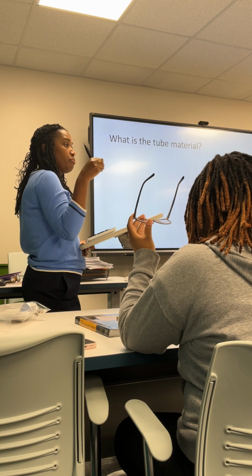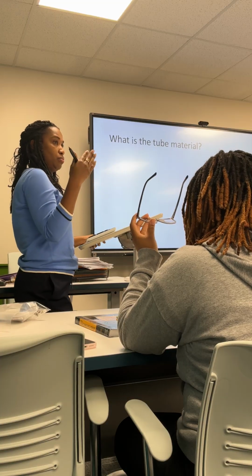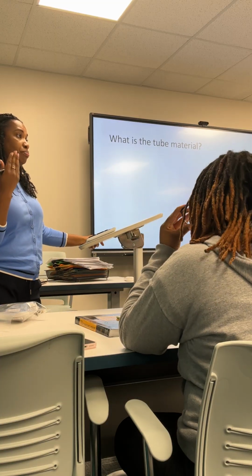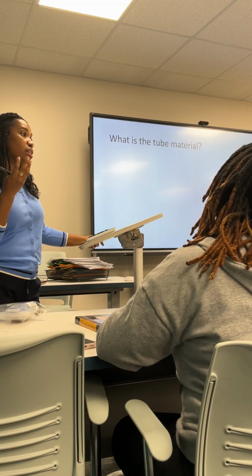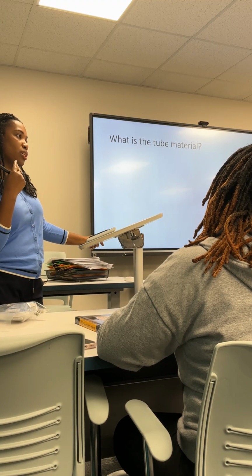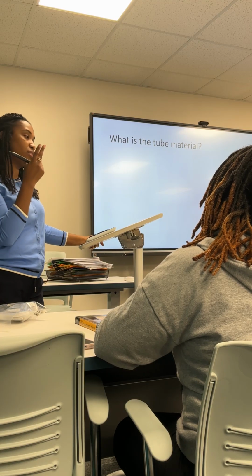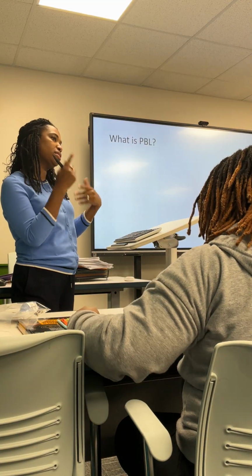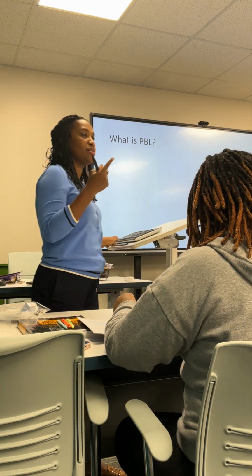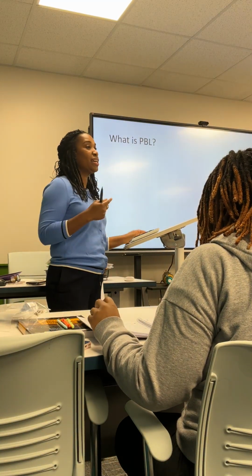What's the filament about? This is the electron source. Y'all listening? The filament heats up. What's the term? Thermionic emission. They're boiled off specifically, right? Yes. How many filaments are in the cathode? It's 2. Small and large. Good. It's almost like a light bulb if you think about it. The filament is sort of a light bulb. Right, it is. Same concept. Also, it's also a diode, right? Giving away answers for later, but yes.